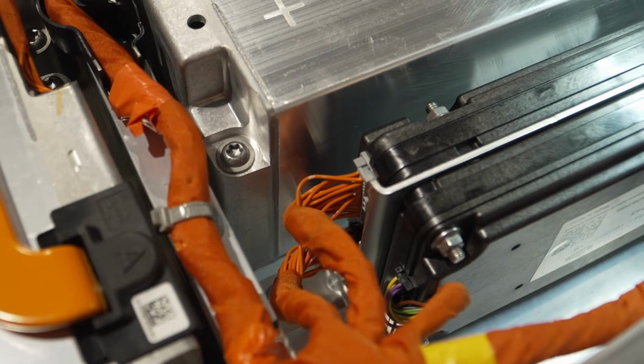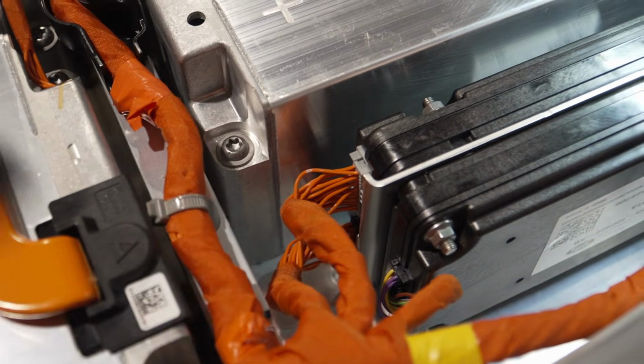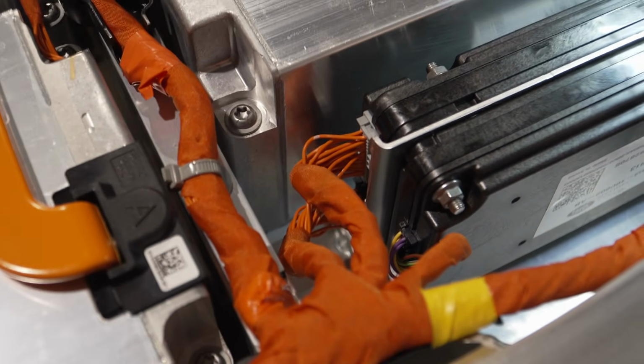Now when we're looking at these modules, we can see on one side we've got 1 connector here. This is going to have our communication lines, the power and ground for that module. And on the other side we're going to have 2 connectors. 1 connector is going to go off to 3 of the batteries, and the other connector to the other 3 batteries as well.